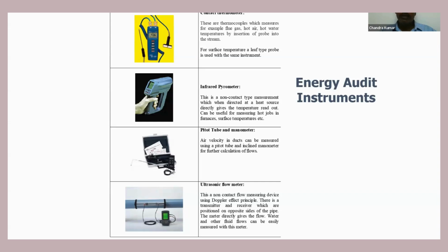Most industries get commissioned by people on the HVAC side during commissioning time. After that, on the maintenance side, there will be some gaps - they won't be able to measure the operating conditions, and it's not easy to measure the air changes per hour happening. So to assess the generation side with the help of the blower, we can see the operating conditions and operational efficiency of blowers. For fans and blowers, we typically use this pitot tube.